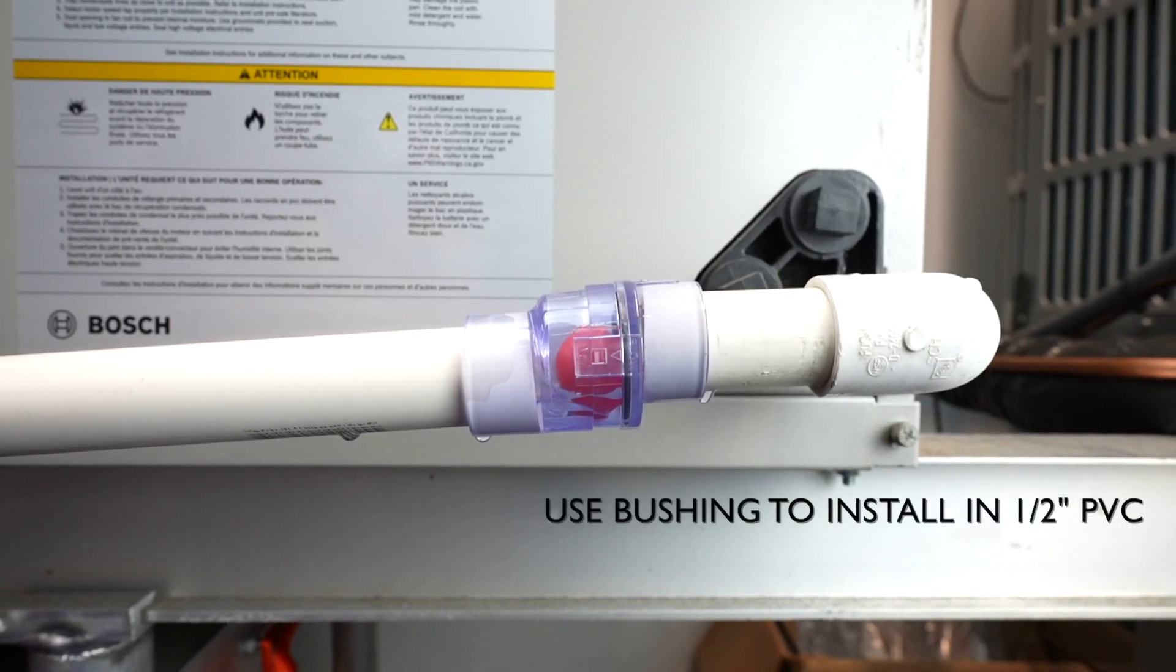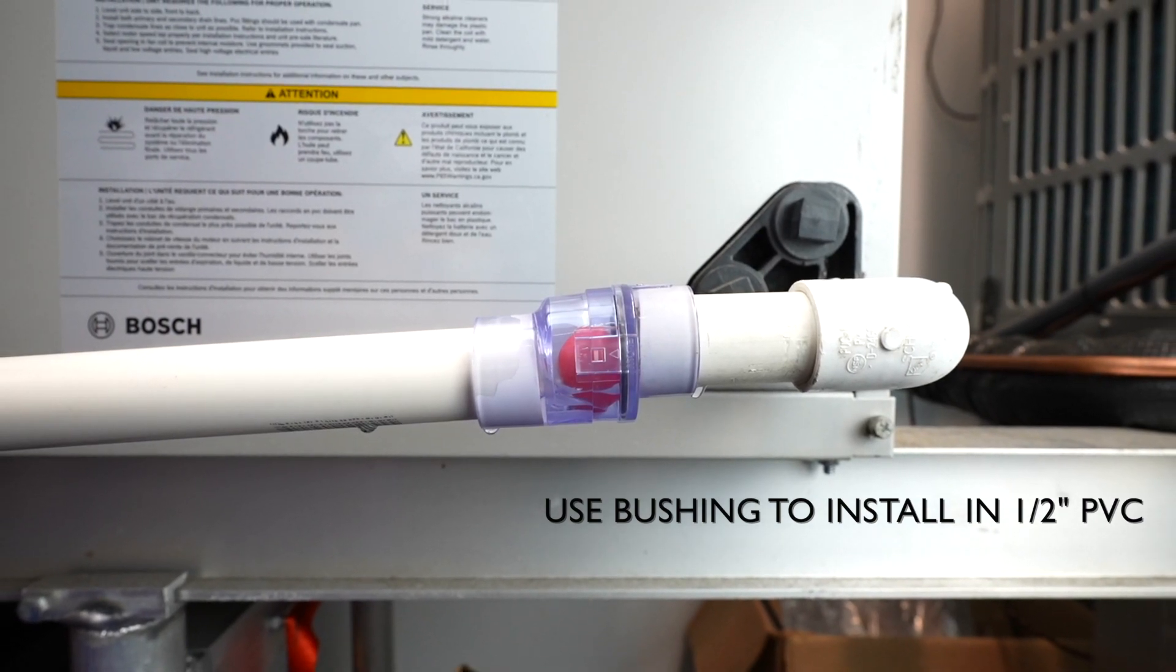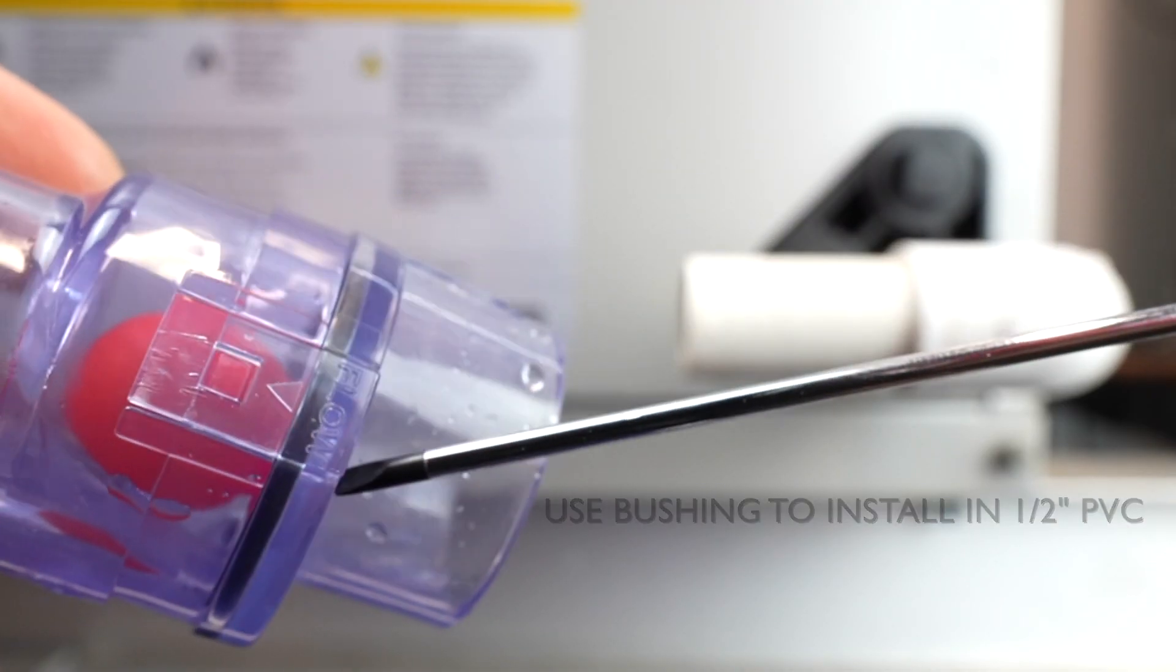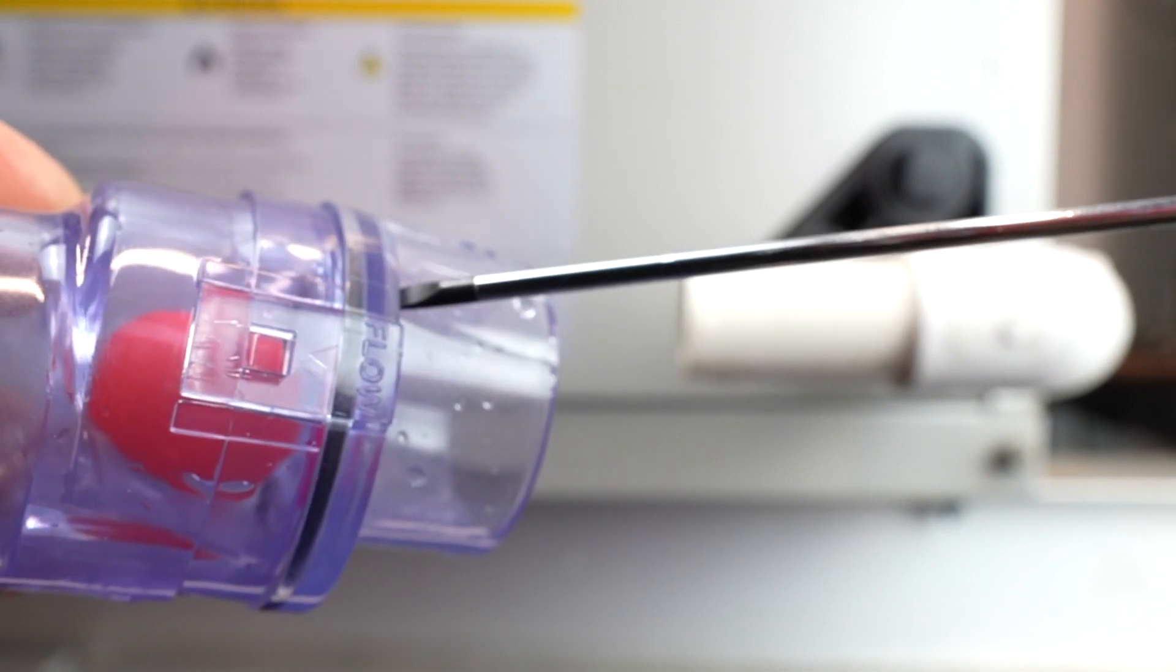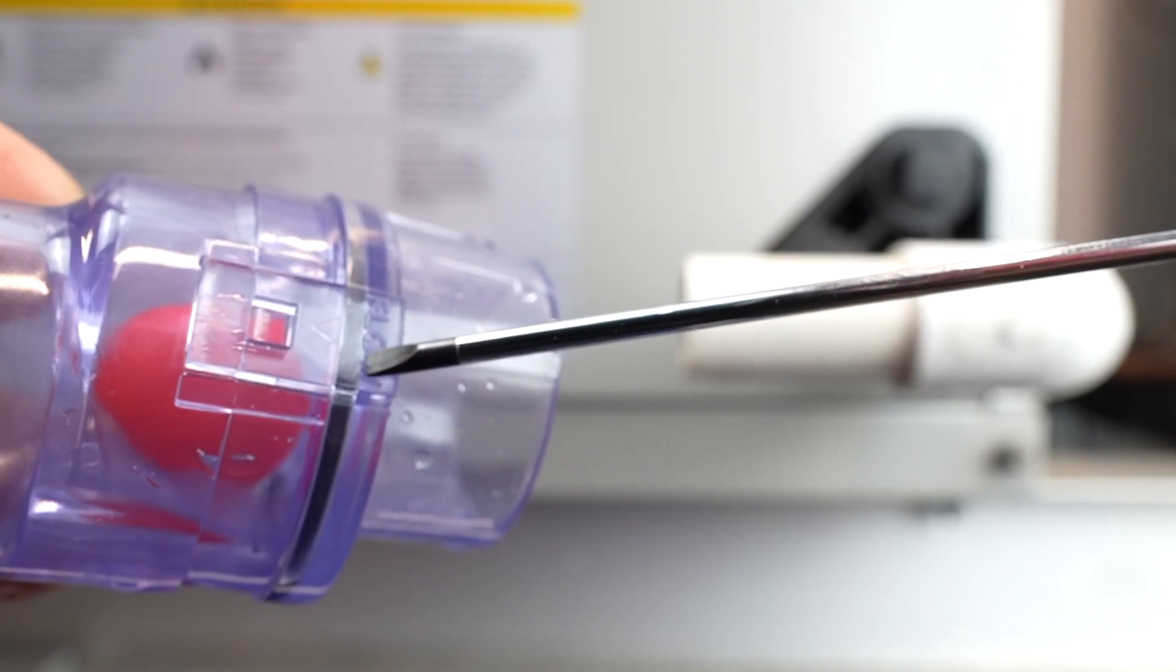Now let's take a look at how easy the W-Trap is to install. The W-Trap is designed to be installed in the horizontal position in a 3/4 inch schedule 40 PVC condensate line. Place the flow arrow on the W-Trap in the direction of the condensate flow.